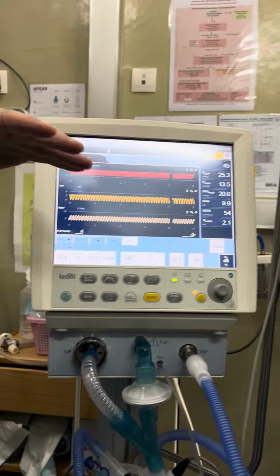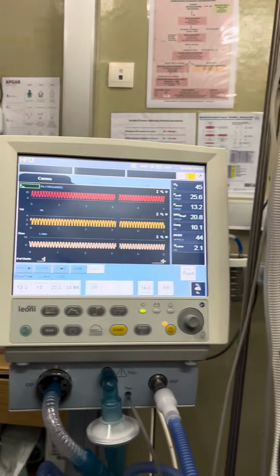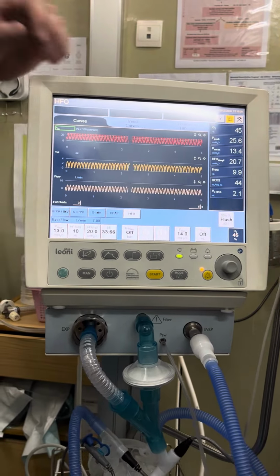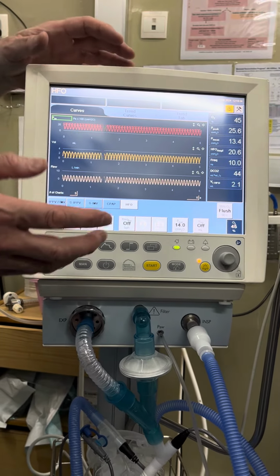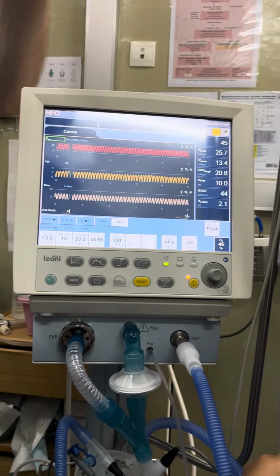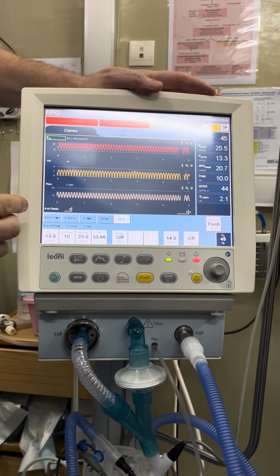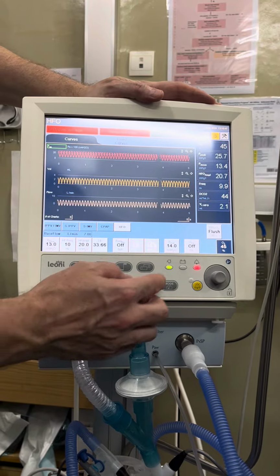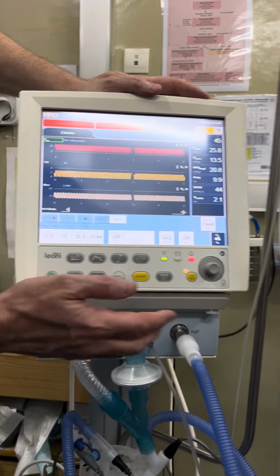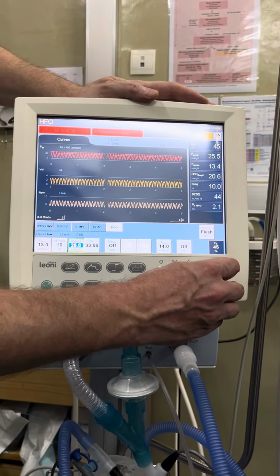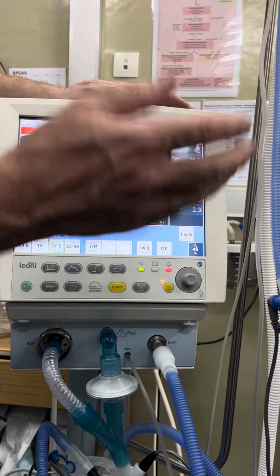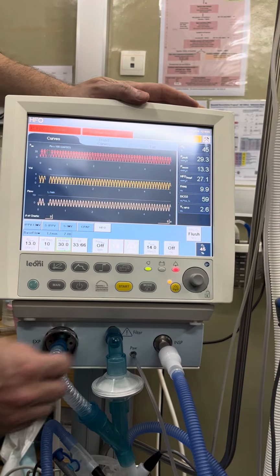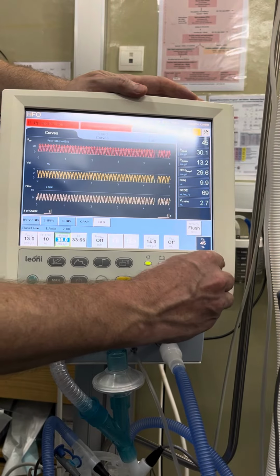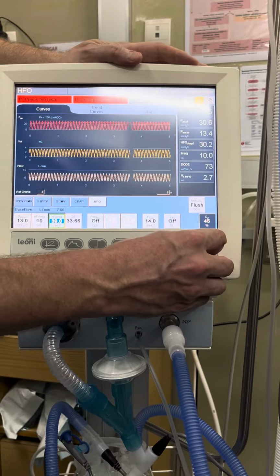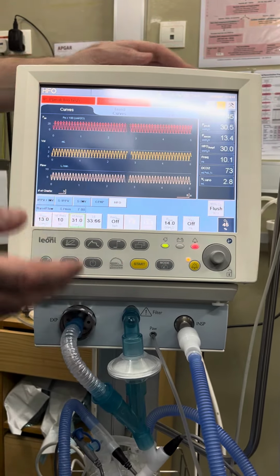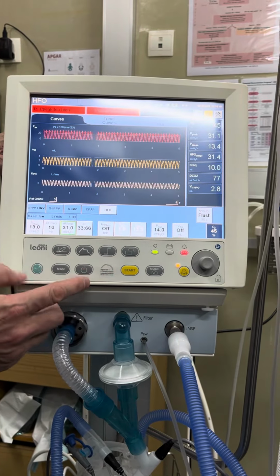So look at the patient. You see now the amplitude of 20 is not much, and you will maybe not see the SpO2 still only on 89, and so this peak pressure is too high. We want to adjust the alarm limits, but first we take up the amplitude. Let's say slowly, 27. The patient was shaking even more. 30. There you go. Now, just to show you what we will not do: not like that. Just slowly up, carefully. 30, maybe 31, and see if the patient is shaking, and then adjust the alarm limits here.